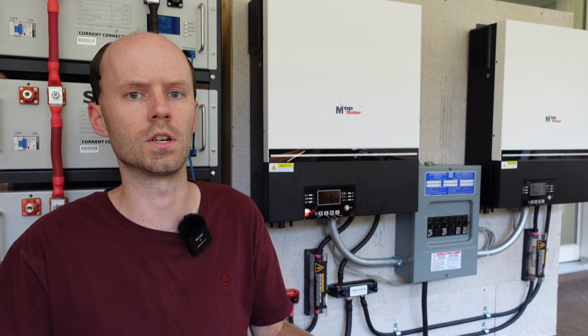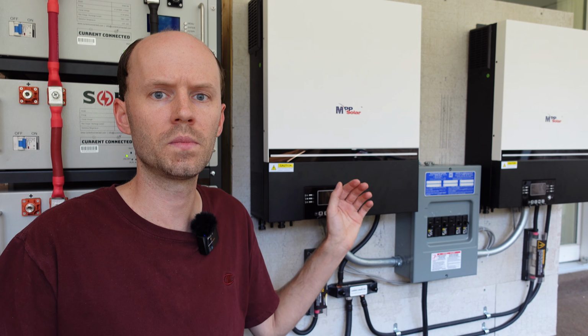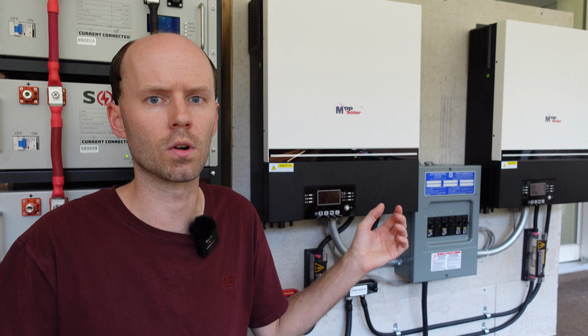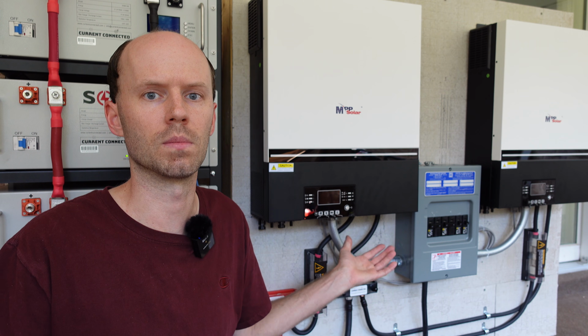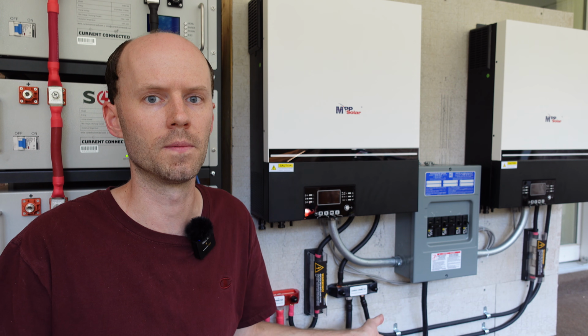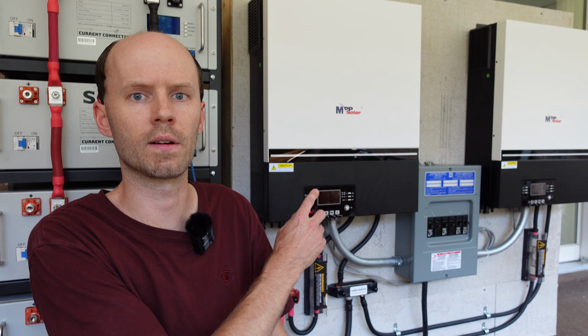All right, so that was a pretty cool test. That clothes dryer ran for about an hour there. There were no issues at all with these inverters. I checked all the cabling, all the connection points. There was no heating issues or anything like that. These did get warm, warm as I would expect them. They weren't overly warm, but I do see why they have those spacing requirements now. You definitely need to allow some ventilation below for the hot air to blow out. These inverters do suck air in from the top and blow it out the bottom. It's kind of against what you would expect, but that is how they are built.